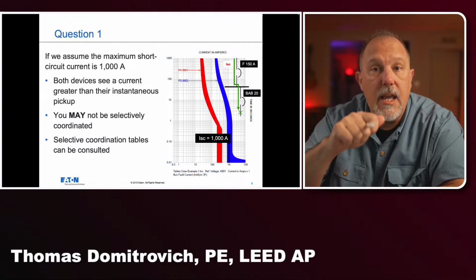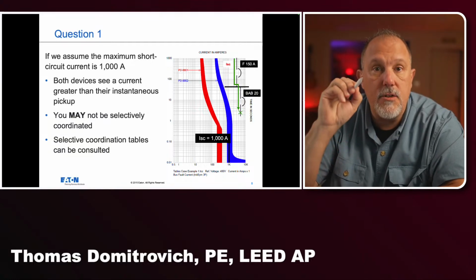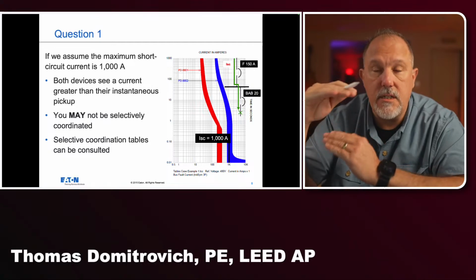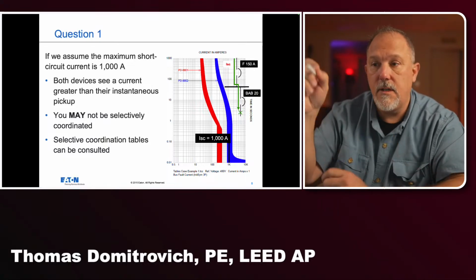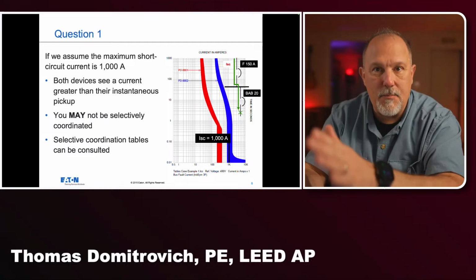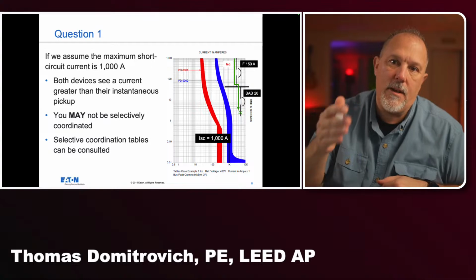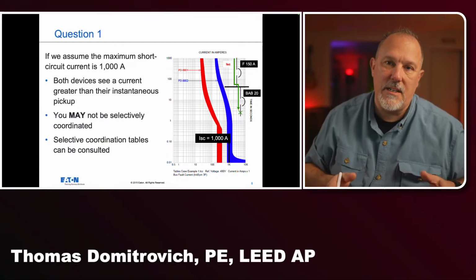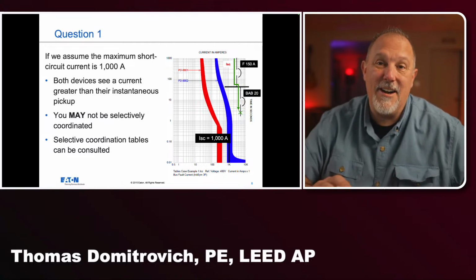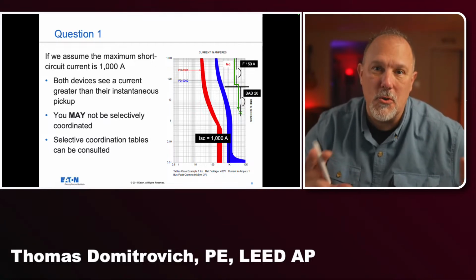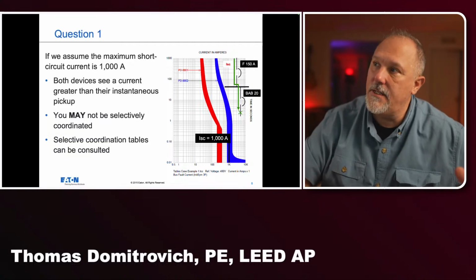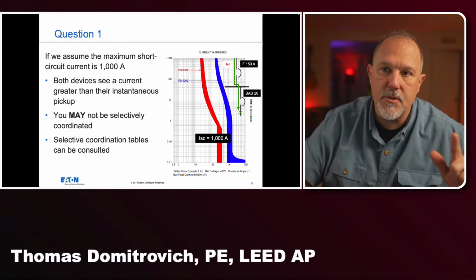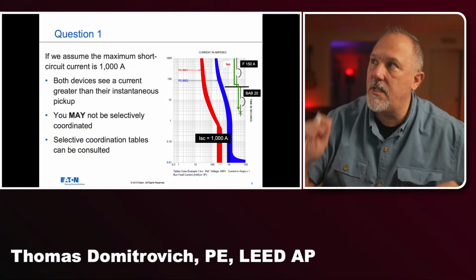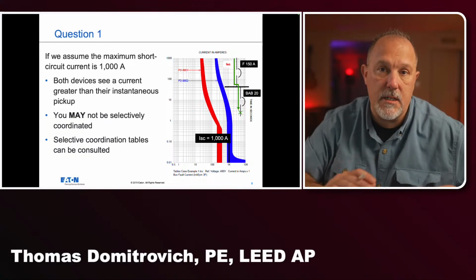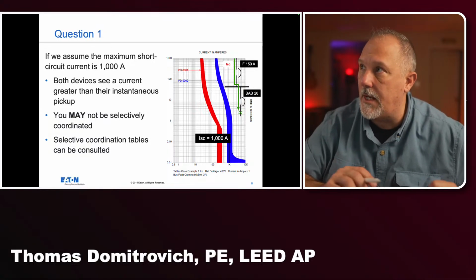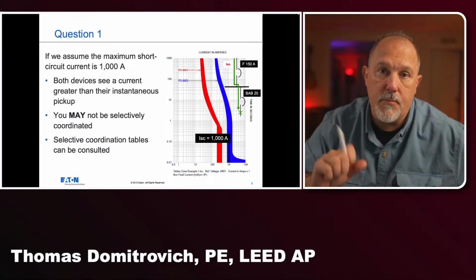When I started using SKM, what I did was I drew the little portion of the TCC and I printed it, cut it out, pasted it, and I copied the page, and I would have that one-line diagram on the actual TCC curve. That was before Adobe Premiere and all these other cool tools. I'm showing my age, but in any case, you need to have the perspective. You need to know what the fault current is that both of those breakers are expected to see. Remember, a fault downstream of that BAB20 is going to be seen by the F-150, the breaker, not the truck.